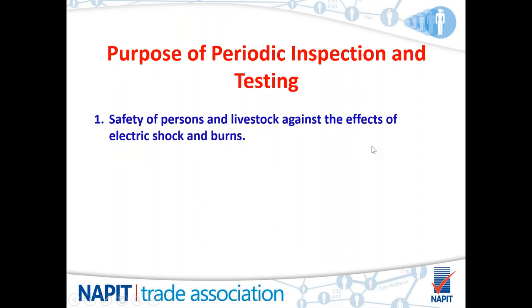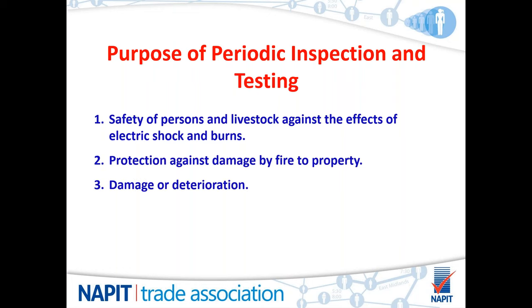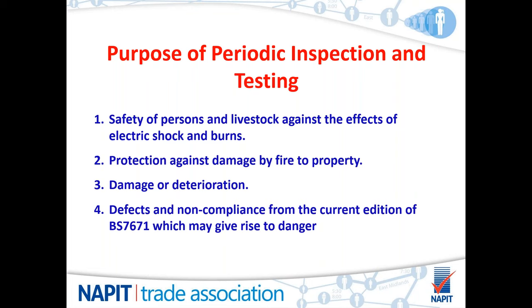Purpose is basically down to what the regs state: safety of persons and livestock against the effects of electric shock and burns, the protection against damage by fire to the property, and any damage or deterioration that you notice through the inspection needs to be reported. Also defects and non-compliance from the current edition of BS 7671. Always the current edition that we make the observations to, which may give rise to danger and therefore make the property unsafe for continued use. And that's the main idea of it.